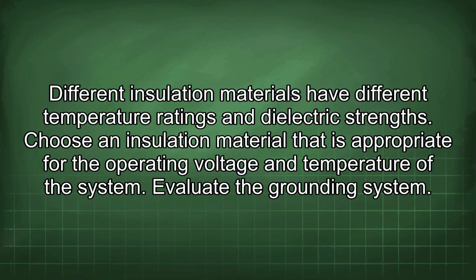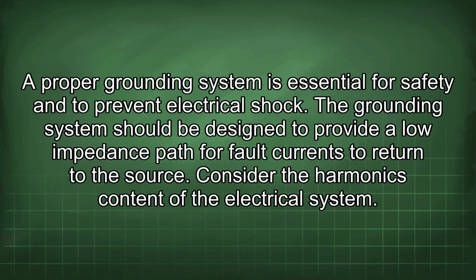Different insulation materials have different temperature ratings and dielectric strengths. Choose an insulation material that is appropriate for the operating voltage and temperature of the system. Evaluate the grounding system. A proper grounding system is essential for safety and to prevent electrical shock. The grounding system should be designed to provide a low impedance path for fault currents to return to the source.